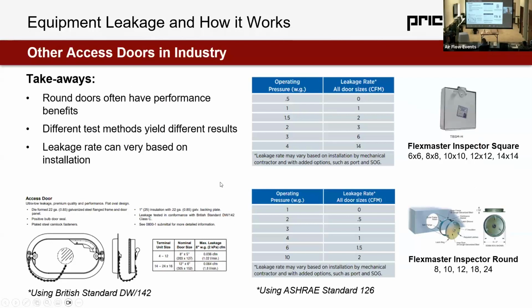Any questions there on access doors? Mark, I think there's one in the chat from Heidi. Okay, I'll check that out really quickly. Heidi asks, any preference for latches versus screws on access doors? If they have the same gasket, it seems the same for leakage. My thought is screws are less preferable because it allows the door to not be replaced during troubleshooting.